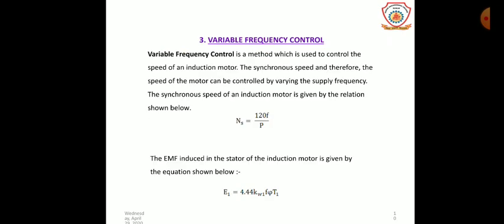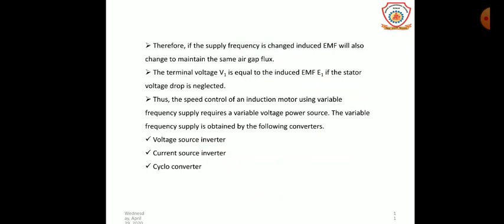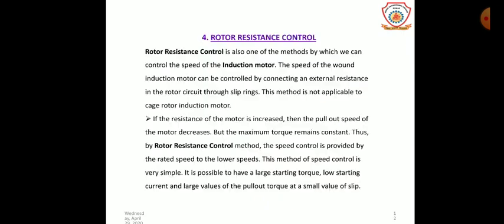The variable frequency control method controls the speed of an induction motor by varying the supply frequency. Since Ns = 120f / P, and the EMF induced in the stator E1 = 4.44 × kw1 × f × Φ × T1, if the supply frequency is changed, the induced EMF is also changed. Variable frequency supply is obtained by the following converters: voltage source inverter, current source inverter, and cycloconverters.